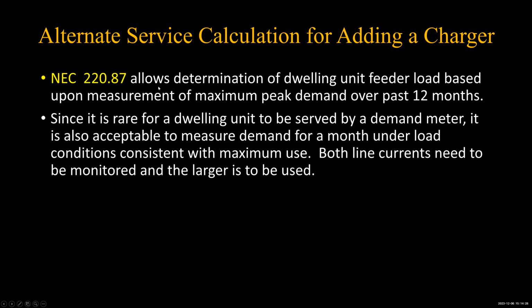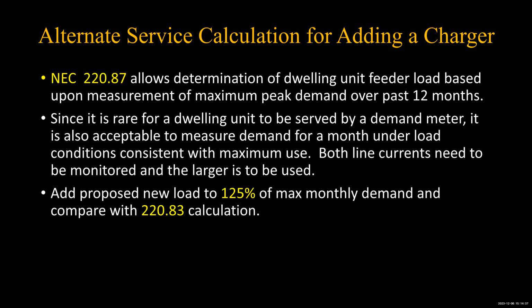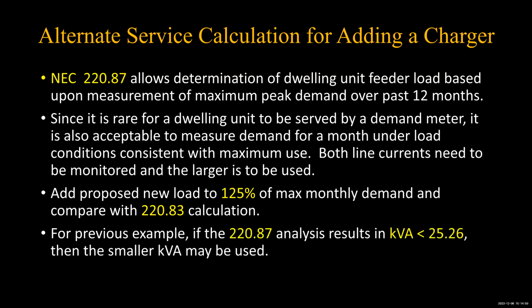But like I said, if you got a general service demand, then you just look at the electric bills and take the highest one of the year and figure out how many amps that is. We're going to come to that. So in any case, 125% of that measured load added to what you got with 220.83. If it's smaller, use it. It's okay. So maybe that can save you the problem of having to, say, go higher than a 200 amp service, or maybe you can set your charger to a higher charging rate.